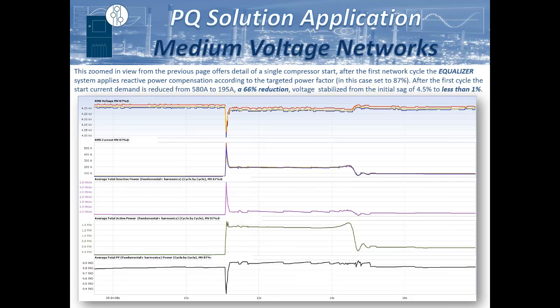Initially, the customer had asked us to set the target power factor at 87. He was an old utility guy, and that made sense, and it's the target he'd always aimed for. So initially we set it to that and took some data, and then I told our guys to go ahead and set it to 98, leave it overnight, come back, and let's capture some data, because we were leaving capabilities on the table here. So you can see here that although this voltage drop occurred, this time period right here is actually less than 2 cycles. So from an equipment perspective, it's not even realized.